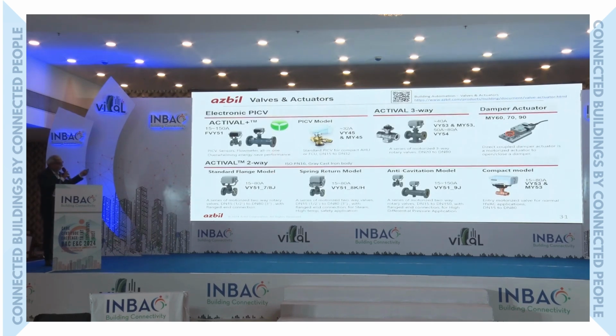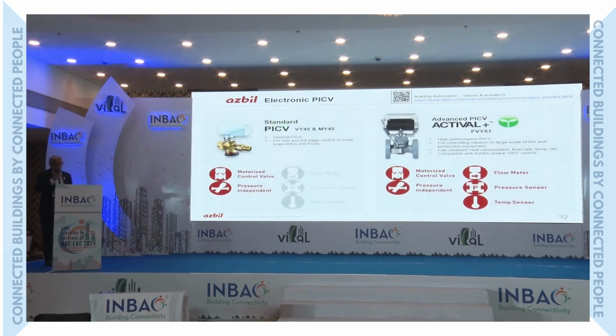This is the regular range of our valves. If you see the valves and actuators, we have multiple types of valves coming from our own basket of products. We also have a standard PICV and advanced PICV. The advanced PICV basically is a combination of a control valve, pressure independent valve, flow meter, pressure sensor and temperature sensor.